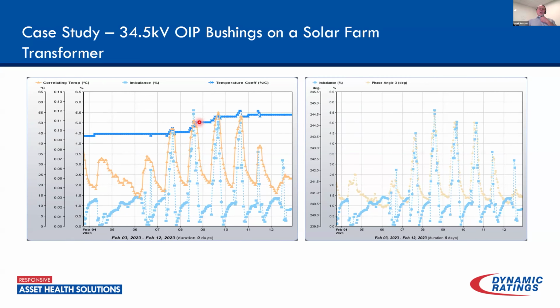In a previous presentation, one of the questions was, when can offline tests be misleading? If there's a lot of moisture in the insulation, power factor tests at lower temperatures can be very misleading. This graph shows it very well. If I'm testing offline at this point, my power factor is going to be down. And if I'm testing at an elevated temperature, when the transformer temperature is high, at this point the power factor is going to be much, much higher. So that could be one indication, and we track that easily with the monitor when I look at that temperature coefficient curve.